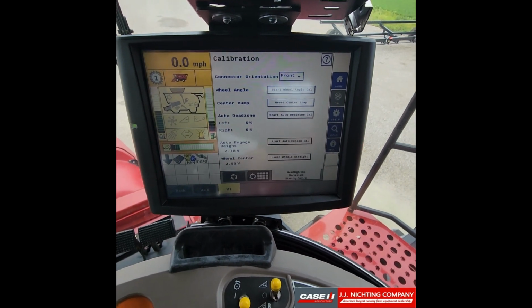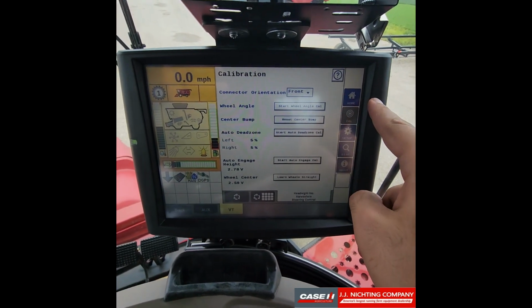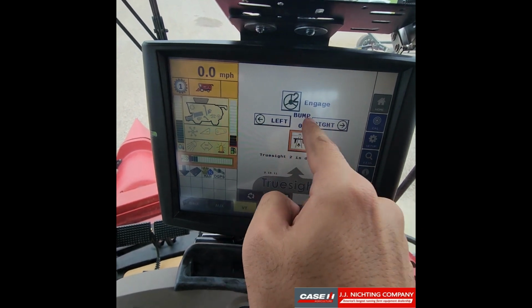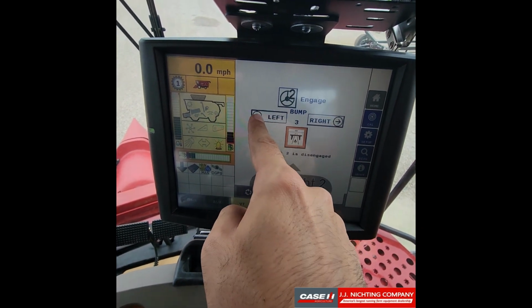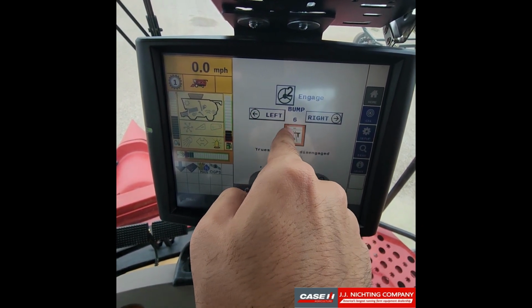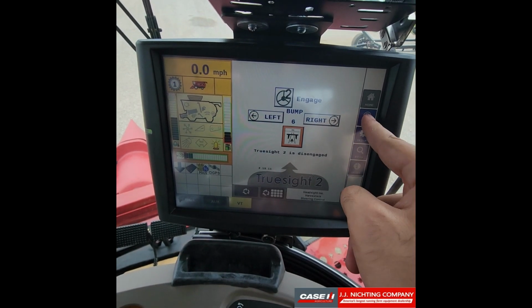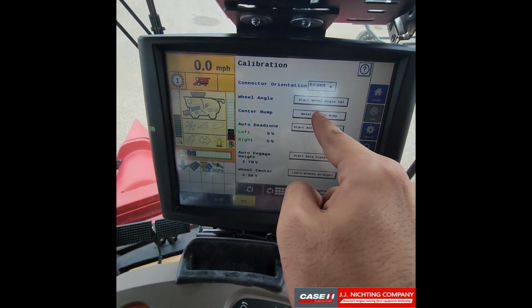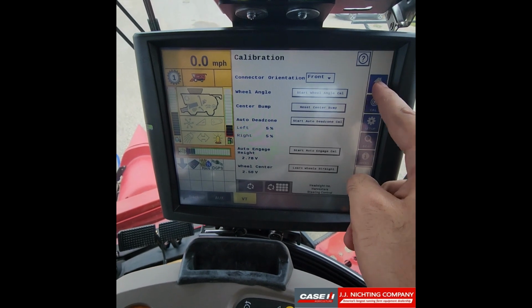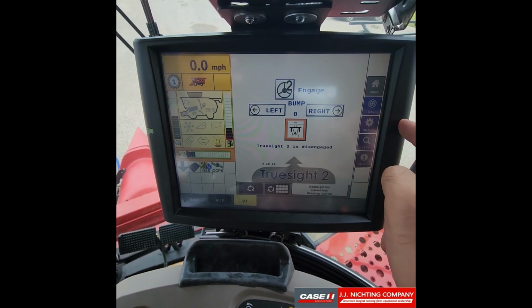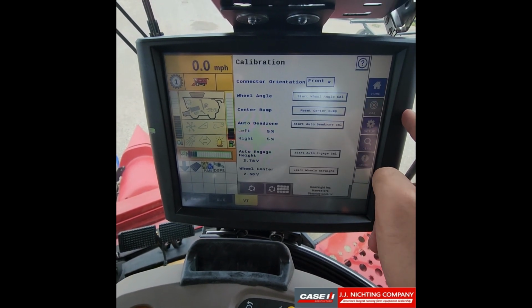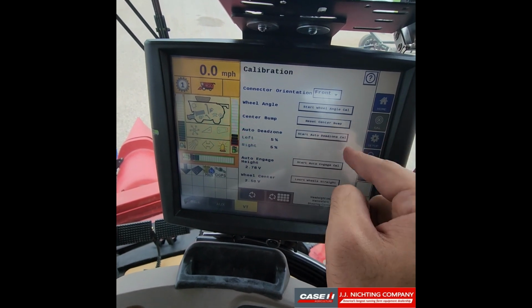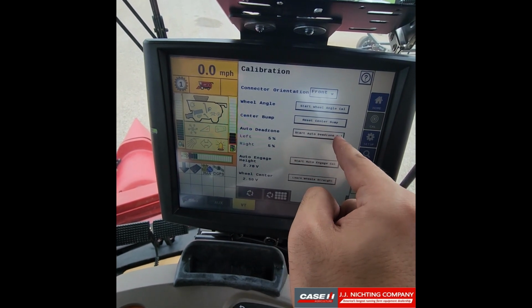And so to use that, we will go ahead and go back to the home tab, and we can adjust our bump either to the left or to the right. And once we have the bump that we want set, we'll go to calibrate, and we will hit reset center bump. And then once we go back to the home screen, you can see it zeroed itself out again. So now we will go ahead and do our auto dead zone calibration.